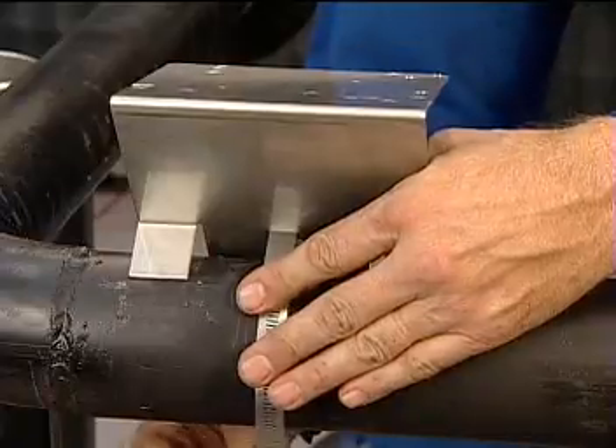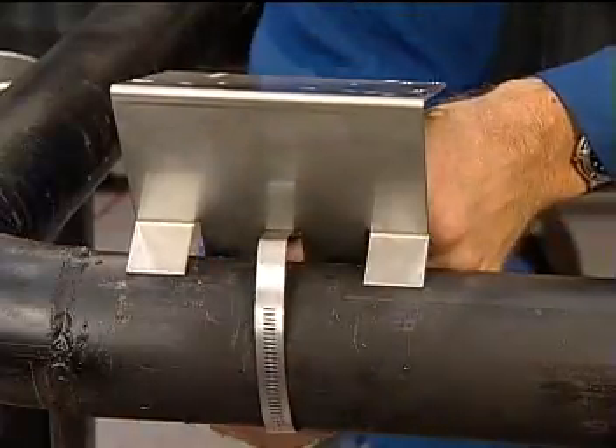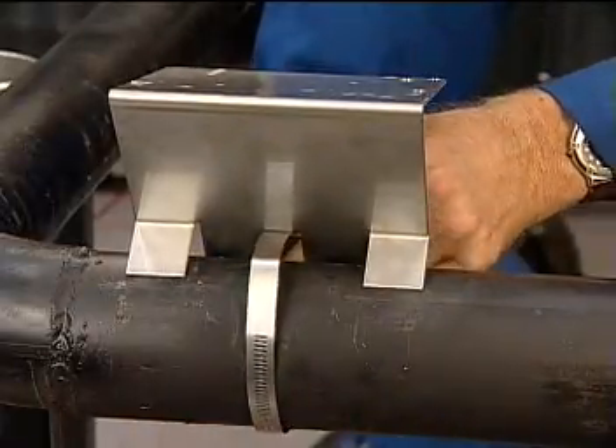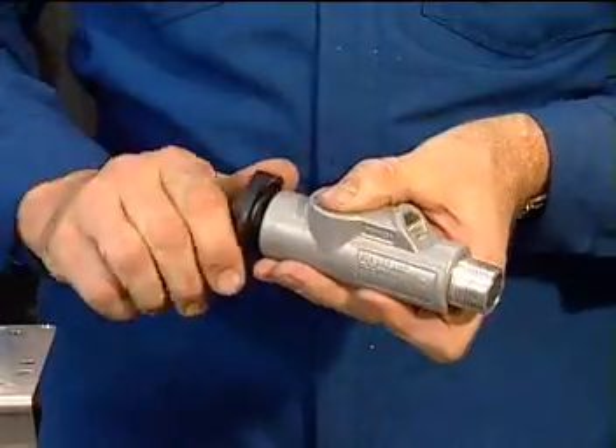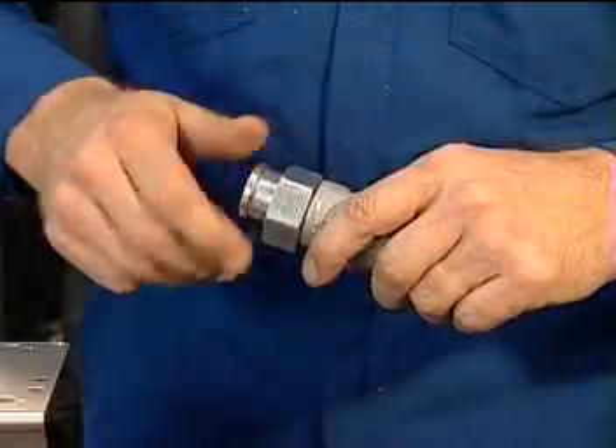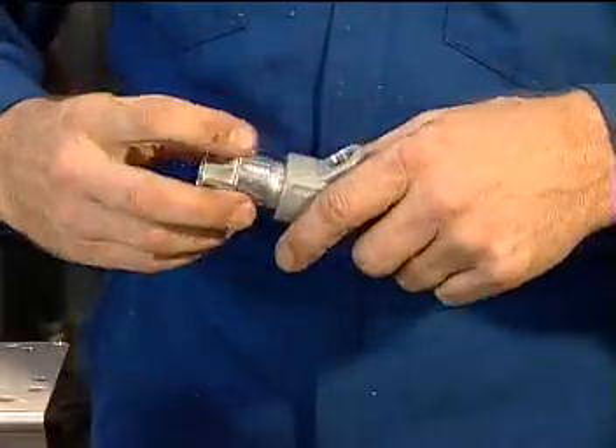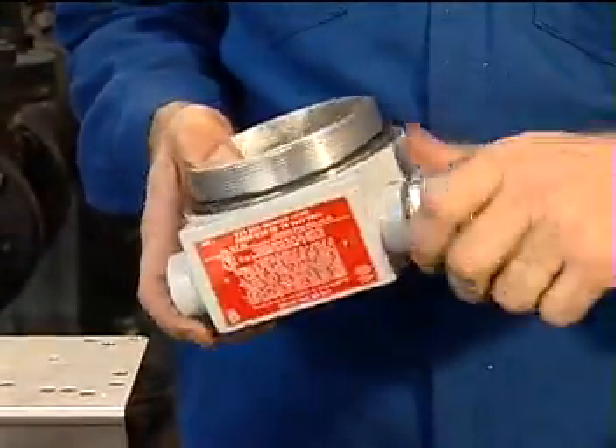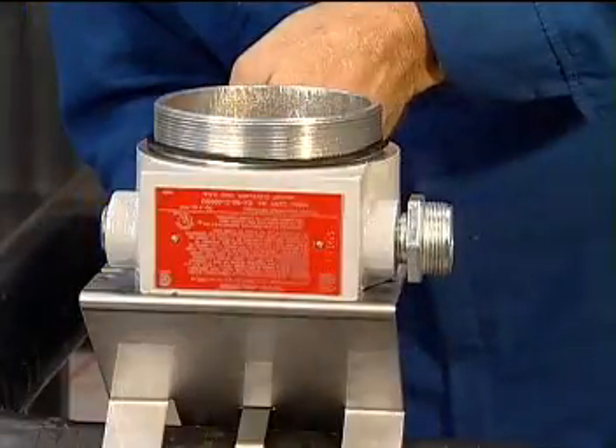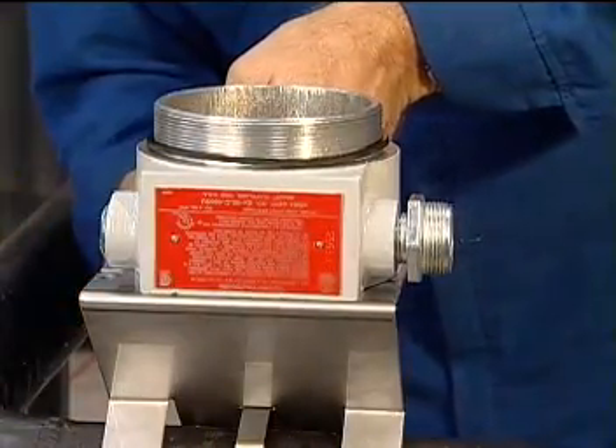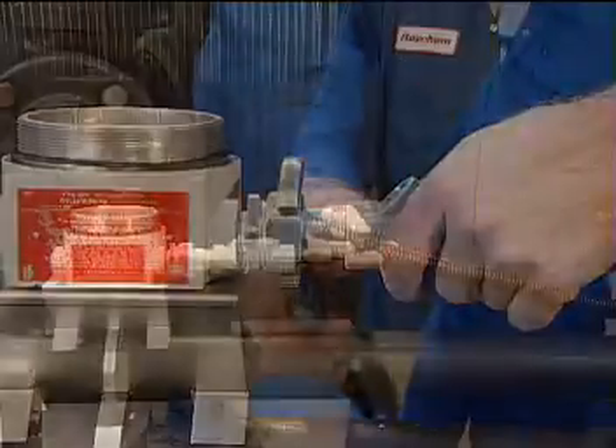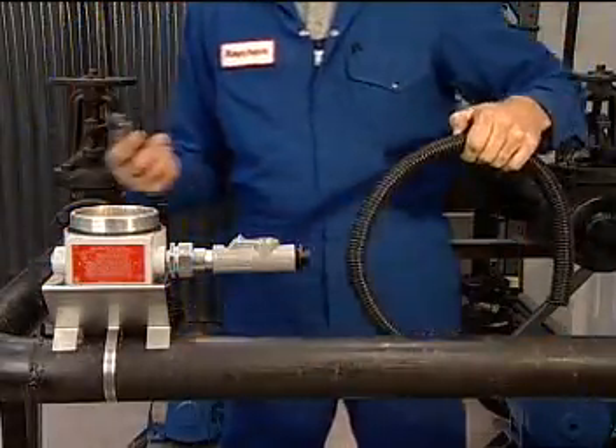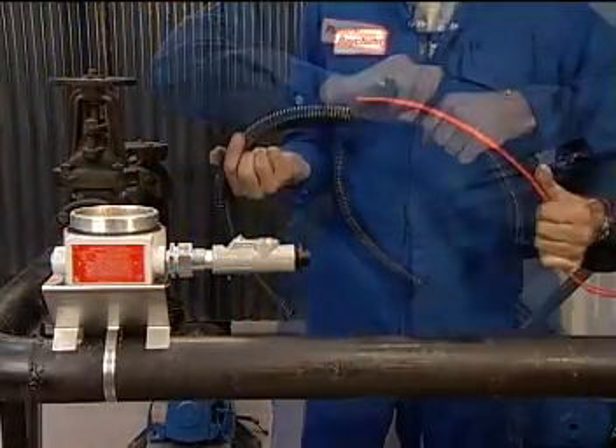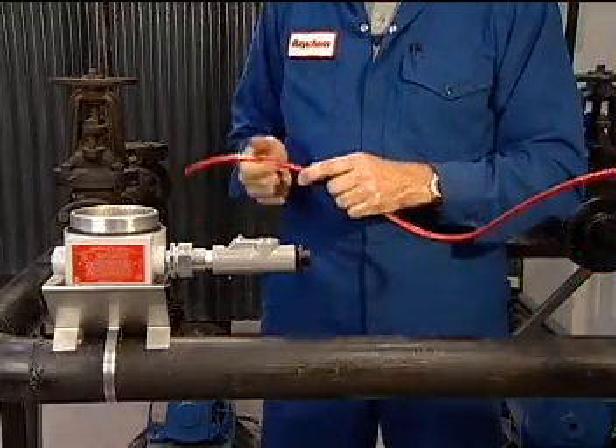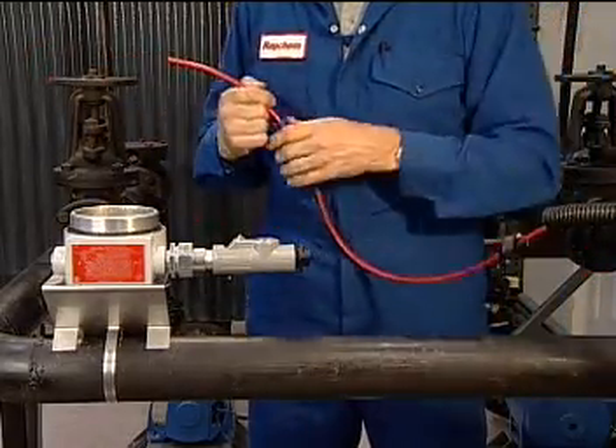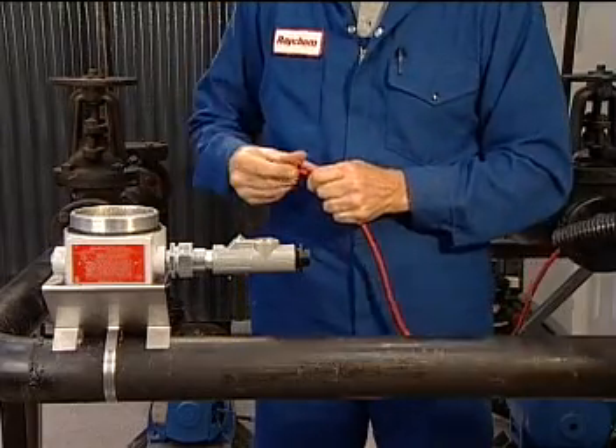To install the HAK C100 kit, begin by installing the UMB to the pipe with the pipe strap. Assemble the half of the compression gland with threaded inserts and the female end of the union to the sealing fitting. Thread the male half of the union into the JB3 box and mount the box to the UMB. Then assemble the union. Cut the corrugated tubing so it's long enough to be taped to the pipe surface when finished. Slide the tubing, its clamp, and the other half of the compression gland over the cable. Select the proper grommet for your cable and slide it on.